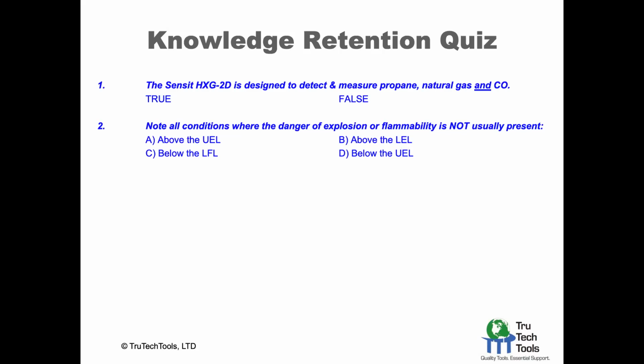So if you can note all the conditions where the danger of explosion or flammability is not usually present. Where is it not usually present? Think back to that chart that was shown within the first few slides there. What is the LEL or the LFL, because it's the same thing, for methane? Is it 5% gas, 50 ppm gas, 100% gas, or 2 ppm gas?